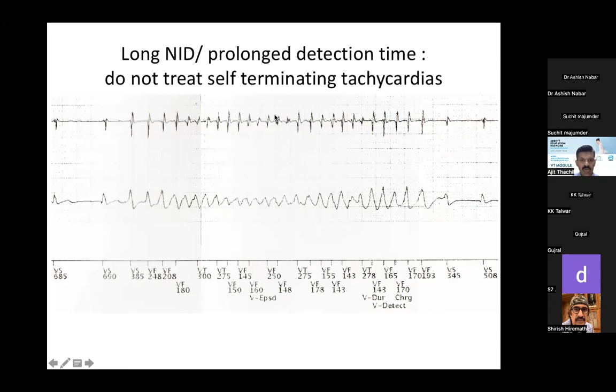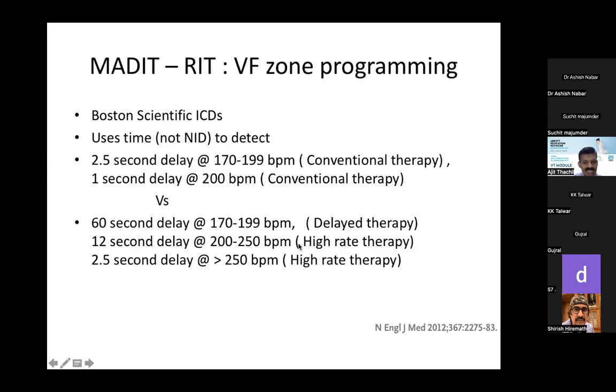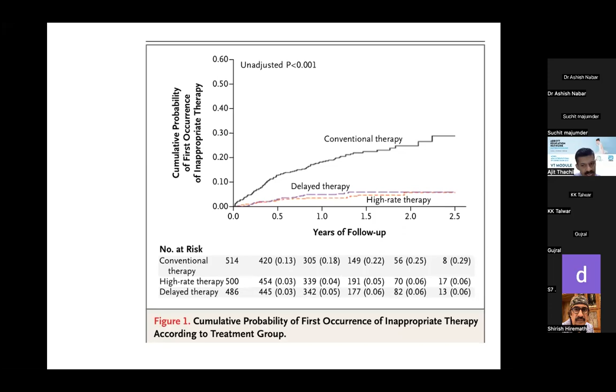There's a trial called MADIT-RIT. It looked at 3 options. One is a Boston ICD. Boston ICD uses time, seconds, rather than number of intervals. So it used 2.5 seconds at 170 beats, 1 second at 200 beats. These are both called the conventional arm. 60 seconds, very, very long, at 170 beats, called the delayed therapy. And then 2 more arms, 2.5 seconds at 250 beats, or 12 seconds at 200 beats, all called high rate therapy. And they found that the delayed therapy and the high rate therapy had fewer inappropriate shocks.